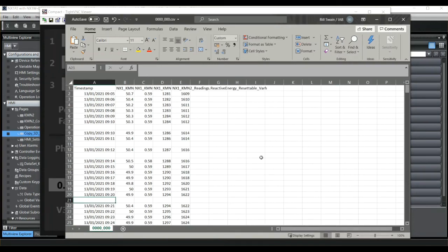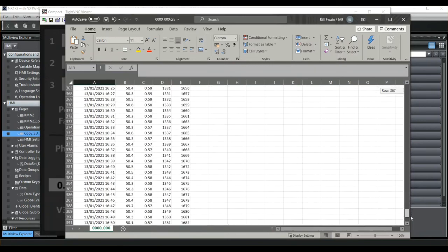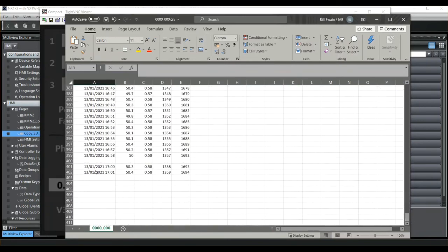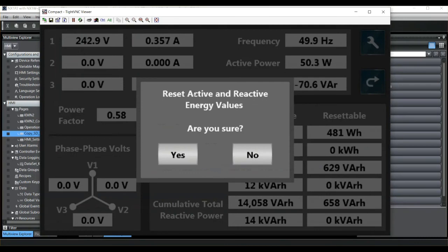The gaps in the data are where the HMI has been rebooted or I've re-downloaded a new application to the HMI, which explains these breaks. But if I scroll down, we basically get a reading every minute for the whole day until I turned off the system. Of course, we could be recording anything else that's held in the controller. Another couple of features: from the main page, if I click on this button here, it asks if I want to reset the active and reactive energy values in the KMN2. If I want to, I click Yes and the controller will send a Modbus command to the KMN2 to reset these values; if not, I just press No.